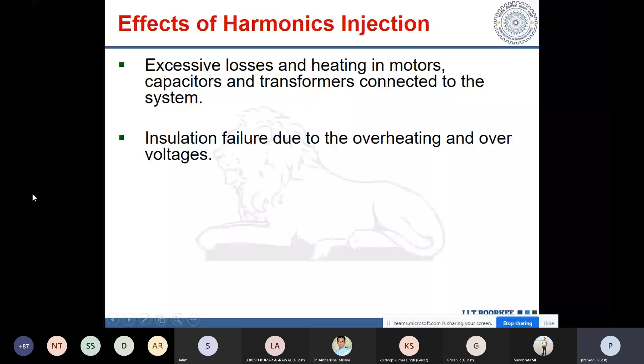Again, let us say you have the fundamental and the third harmonic only, just consider these two components. Fundamental plus third, depending upon the phase relation, you may get a nearly flat top, or you will get a more peaky voltage. Magnitude wise, the fundamental and third harmonic are the same in both cases. But if you find the peak value, in one case it will be much higher, and in the other case it is reduced. If the peak value of the voltage becomes higher, insulation is subjected to excessive voltage. There is a possibility of insulation failure, and of corona discharge because of this overvoltage, so loss of conductor life.